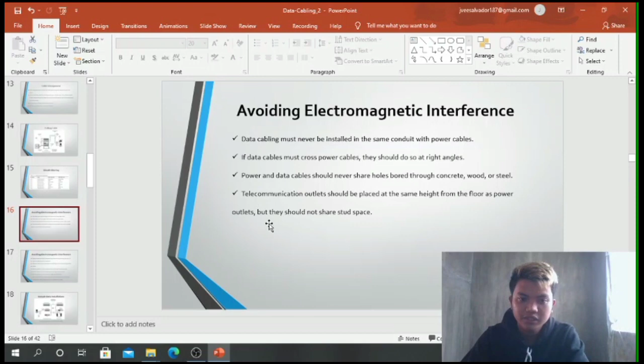Sharing and avoiding electromagnetic interference: data cabling must never be installed in the same conduit with power cables. If data cables must cross power cables, they should do so at right angles. Power and data cables should never share holes bored through concrete, wood, or steel. Telecommunication outlets should be placed at the same height from the floor as power outlets, but they should not share stud space.